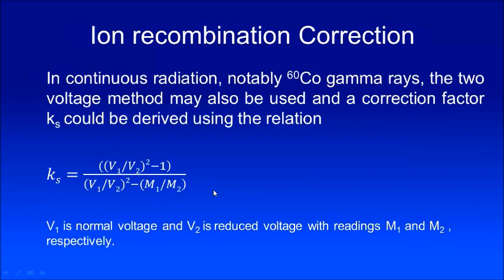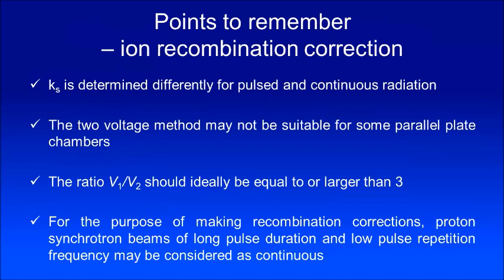Some points to remember for ion recombination correction: K_s is determined differently for pulsed and continuous radiation. The two-voltage method may not be suitable for some parallel plate chambers. Importantly, V1/V2 should ideally be equal to or larger than 3 — so use 300 and 100, or 400 and 100. For the purpose of recombination correction, proton synchrotron beams of long pulse duration and low pulse repetition frequency may be considered as continuous beams.